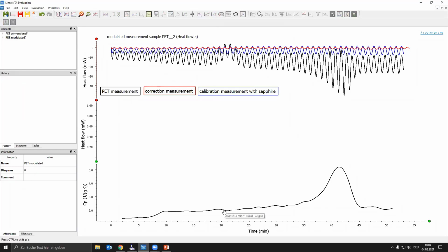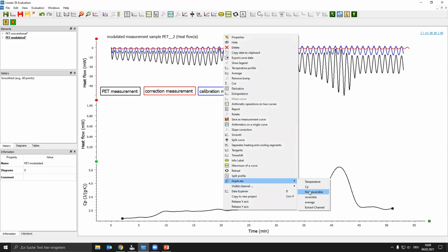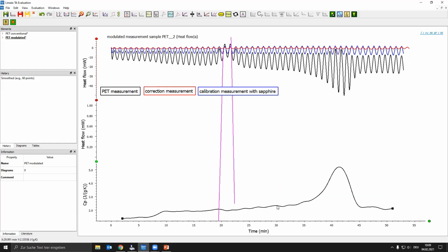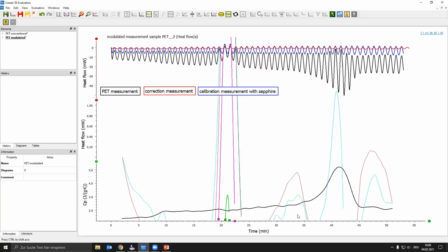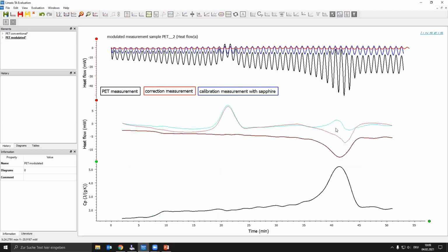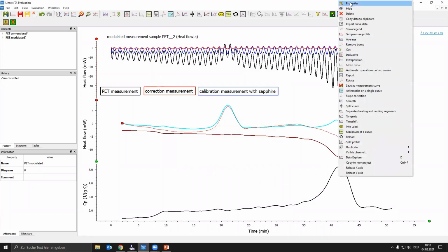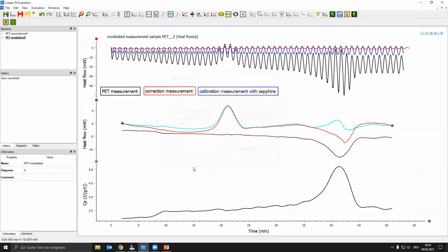But now let's talk about the other information we could show here. So it's the non-reversing part, the reversing DSC signal, and of course the average DSC signal. Those two curves I want to correct by baseline. This is a new automatic tool we use here. And now let's plot them, zoom out, and for a better visibility, of course, it's possible to make this curve visible here. And now we can find all information we could receive with our modulated DSC measurement.